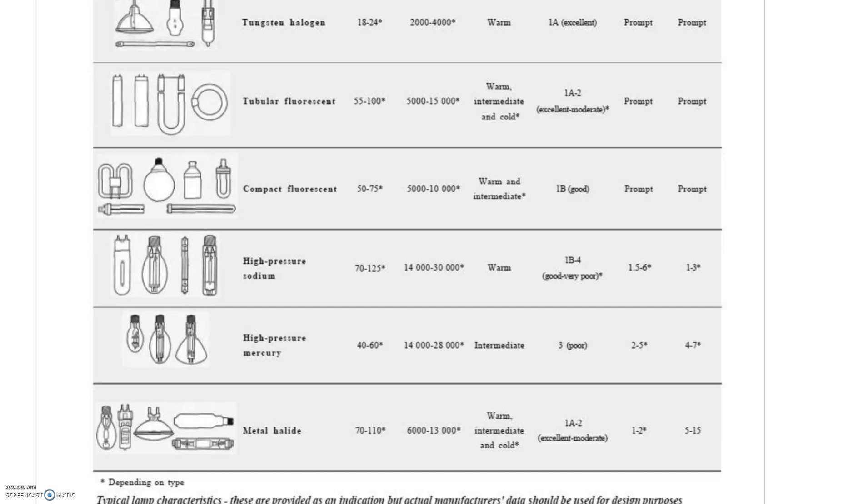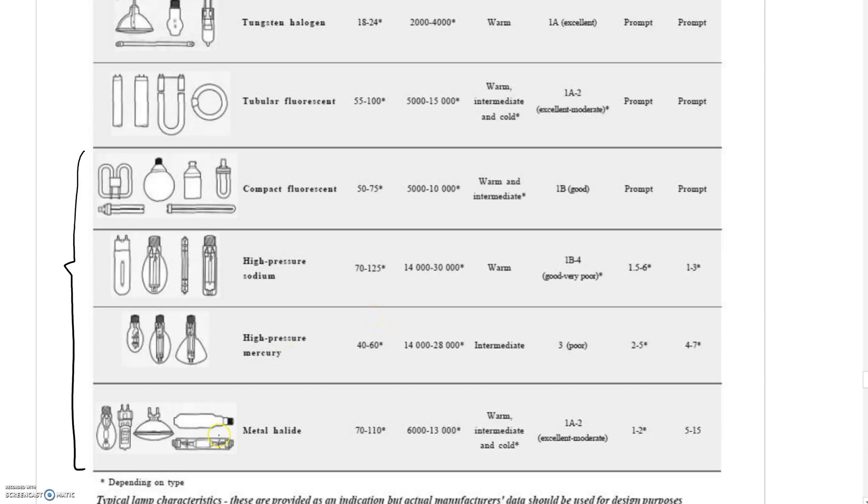These are all discharge lighting working on metallic gas which vaporizes to give light. High pressure mercury and sodium are used for warehouse lighting. Metal halides give good color rendering for football pitches and sports fields where you need the right color, producing a whitey-green tint.